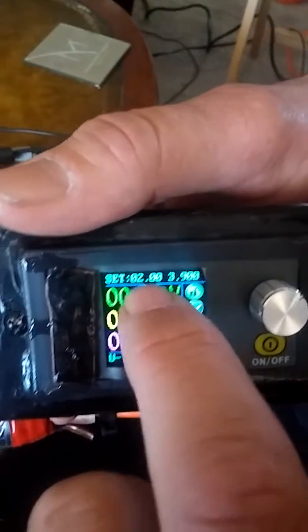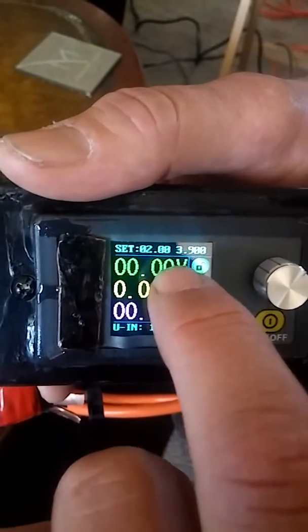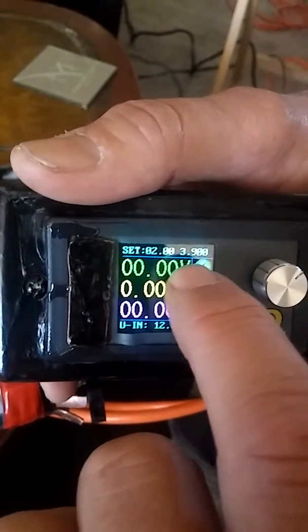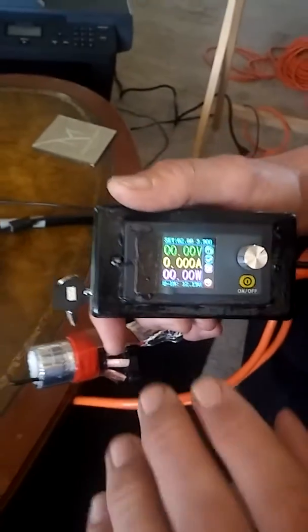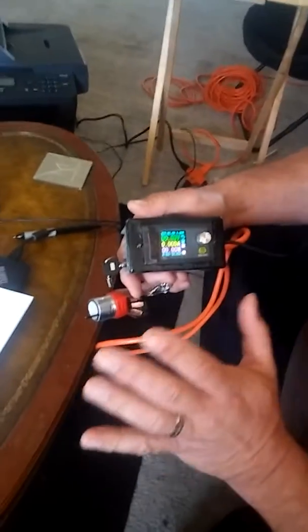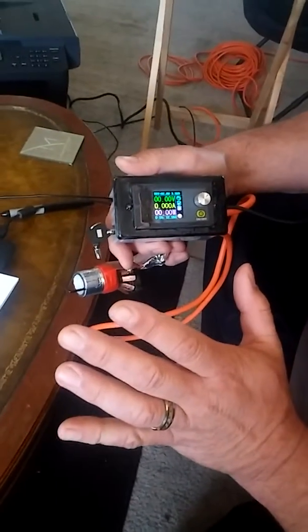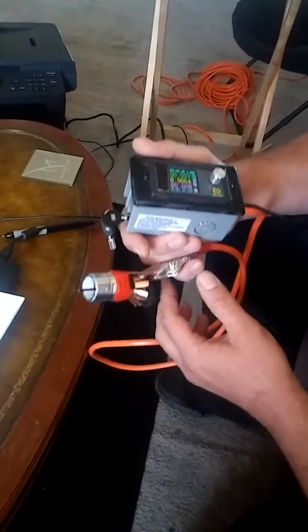0-2, that's your voltage, and then 3.9 to 4, depending on the rating on the diodes of the lasers that I build, but it should be within that range. If it's not, call me, get a hold of me, and we'll get it recalibrated. It should never be a problem, but just in case, you don't want to fire the laser at the wrong settings or you'll damage the laser head.